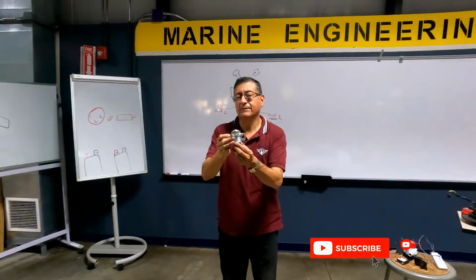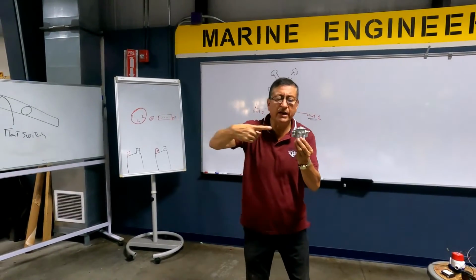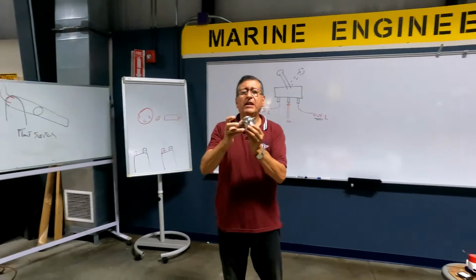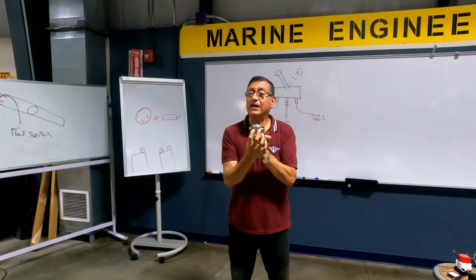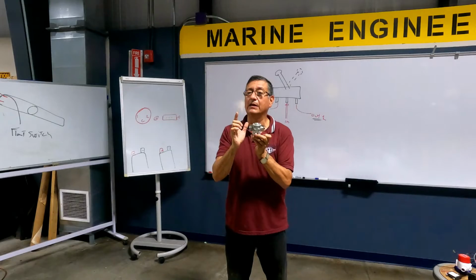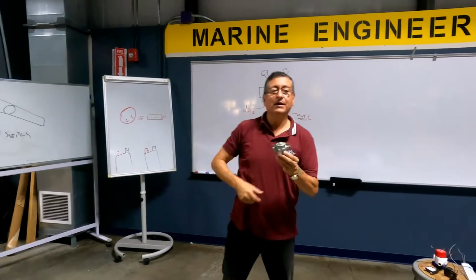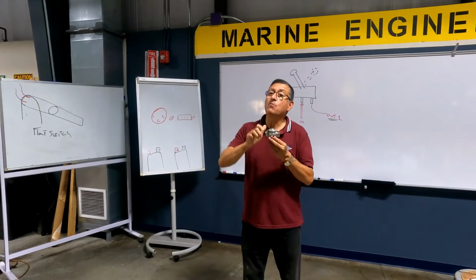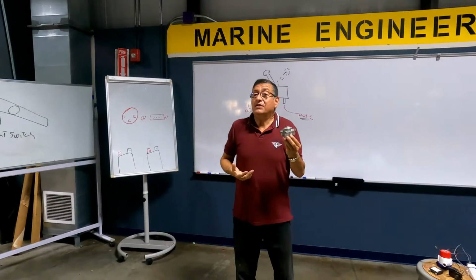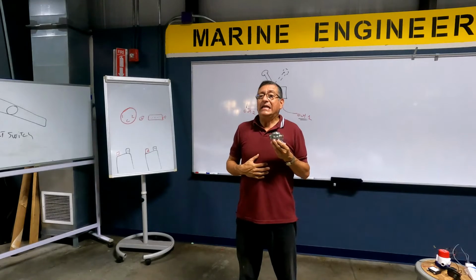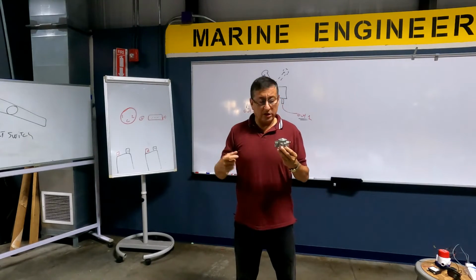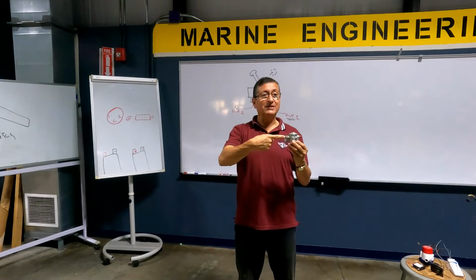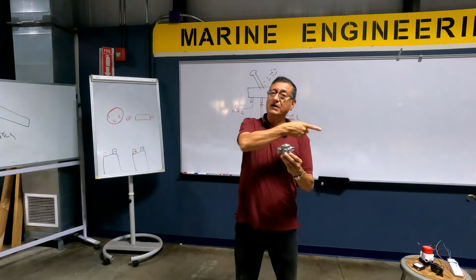Look at this. This is a switch. I have the current entering here, and I want to continue here. In this moment, it's open. When I bring the signal, what happens with the contactor internally? It closes, and the current passes. This is a switch remotely activated. It's used in applications when I need to interrupt the flow of big current. Normally, the cable that enters here carries 50 amps, 60 amps, 100 amps.